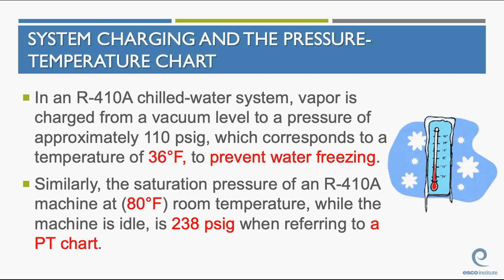In an R410A chilled water system, vapor is charged from a vacuum level to approximately 110 psi. In a chilled water system, we have to charge with vapor first. 110 psi is about 36 degrees Fahrenheit, which will prevent the water from freezing on the water side of the system. Be very, very careful with chilled water systems. If you charge them with large amounts of liquid refrigerant, you will freeze the water on the water side of the system.